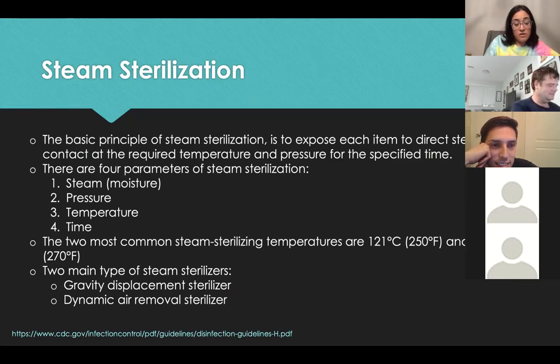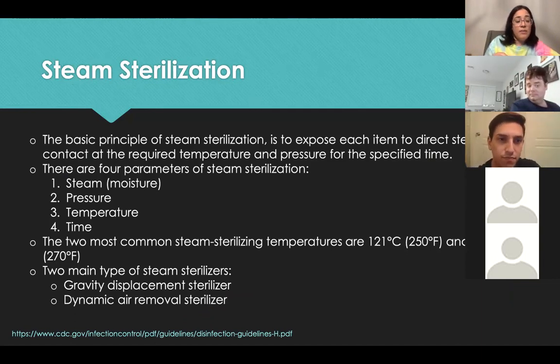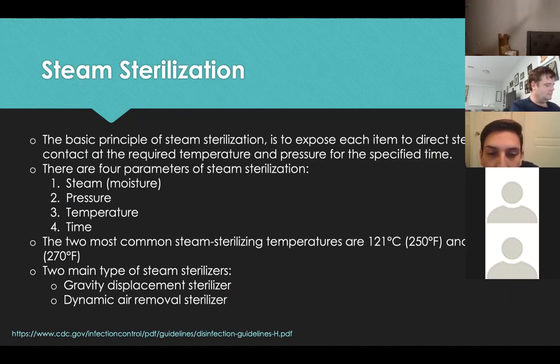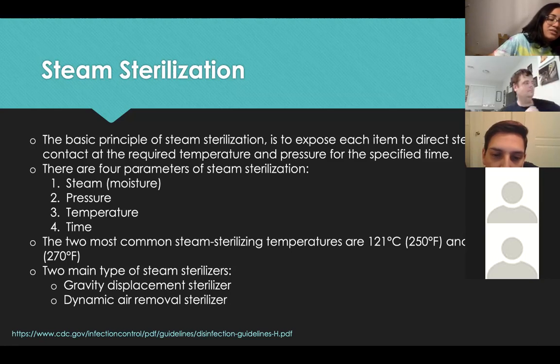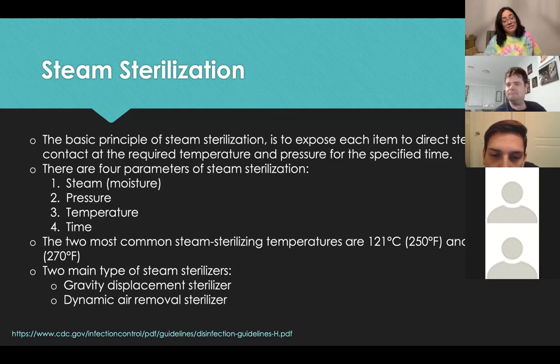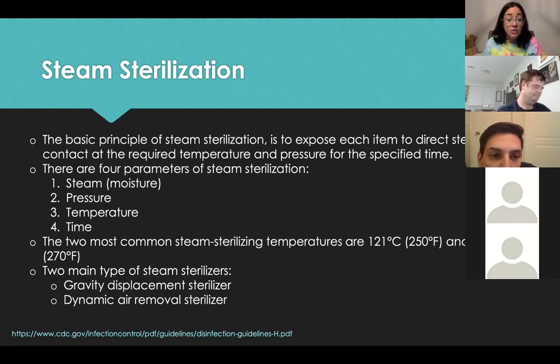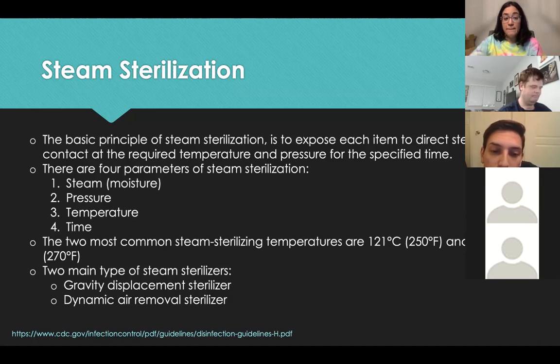There are four basic parameters to focus on for steam sterilization: steam or moisture, pressure, temperature, and time. The two most common steam sterilizing temperatures are 250°F and 270°F. This is really important — you will be asked about temperatures for the different sterilization methods on the exam.